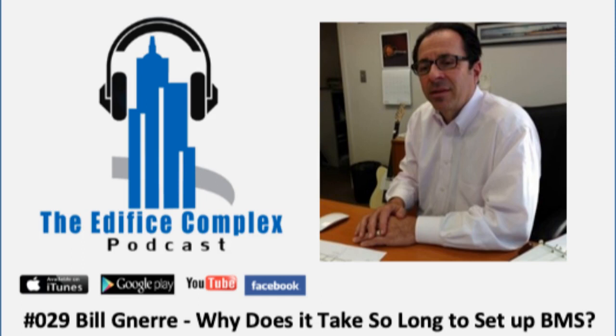Current state of play on a job I was on recently was there was a great chiller, and it had this bespoke internal software running it, and all the BMS or BAS could do was send a run and enable signal to it. Otherwise, there was no data acquisition that the BMS could do. So you had this quite intelligent chiller, a reasonably intelligent BAS system, and they weren't really talking well to each other other than please turn on, please turn off, which sort of defeated the object in a way, I thought.